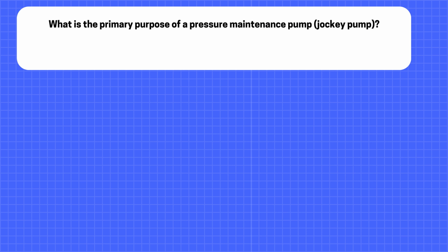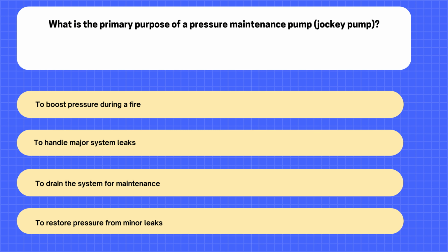What is the primary purpose of a pressure maintenance pump, jockey pump? A. To boost pressure during a fire. B. To handle major system leaks. C. To drain the system for maintenance. D. To restore pressure from minor leaks.